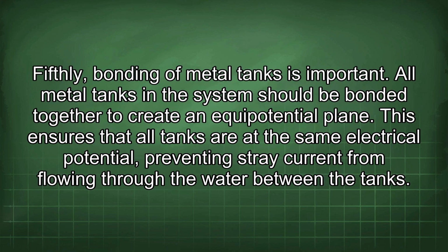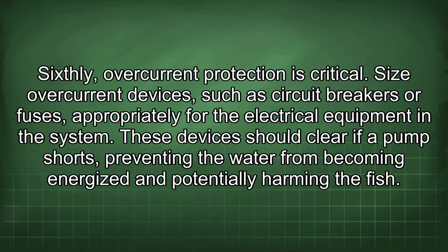Fifthly, bonding of metal tanks is important. All metal tanks in the system should be bonded together to create an equipotential plane. This ensures that all tanks are at the same electrical potential, preventing stray current from flowing through the water between the tanks. Sixthly, overcurrent protection is critical.